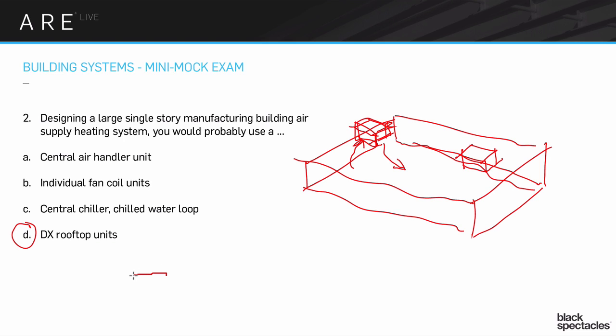What we were looking at in the previous question was a chiller, and that chiller had a refrigerant loop. And then it went on to two barrels and this was all part of the chiller, and it created a cold water loop that went up and gave the chilled water to the air handling units wherever they were anywhere around the building. And then the air handling units have what's referred to as the air side loop.